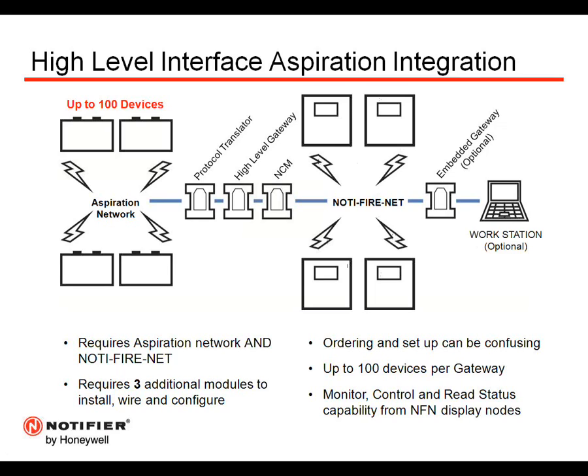Required at least up to 3 additional modules, again, that required to be purchased, installed, wired, and configured. And we find that the ordering and setup can be somewhat confusing for some of our customers. With this high-level integration aspiration, we could support up to 100 devices per high-level gateway. It does offer the ability for monitor control and read status capability from NOTI-FIRE-NET display nodes. And the NOTI-FIRE-NET display nodes would either be an NCA2 on the NOTI-FIRE-NET network, ONYX Works workstation on a NOTI-FIRE-NET network, or an NFS2 3030 operating in network annunciator mode, also otherwise known as hybrid mode.